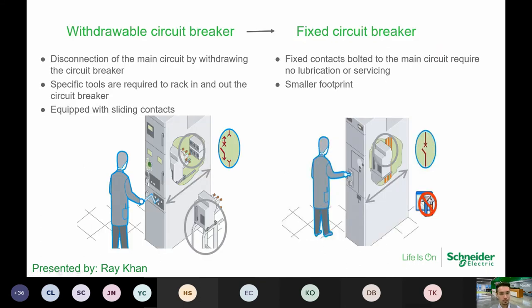Okay, so this picture again talks about the AIS where you have to rack out the switchgear, the withdrawable circuit breaker, all right, to a safe location where you can actually do the maintenance. Right, whereas for GIS, the circuit breaker cannot be withdrawn. The benefit of it, if it cannot be withdrawn, means there's no mechanism for racking in and out. This reduces the mechanism. You don't have to do any lubrication or servicing. And also the footprint is much smaller because of the gas, right? Especially when it comes to Singapore design, we are always facing a space issue.